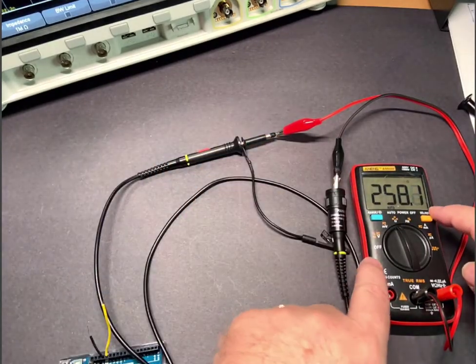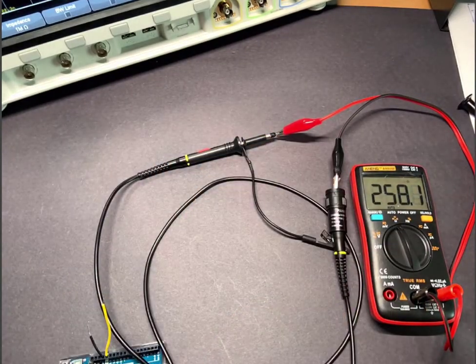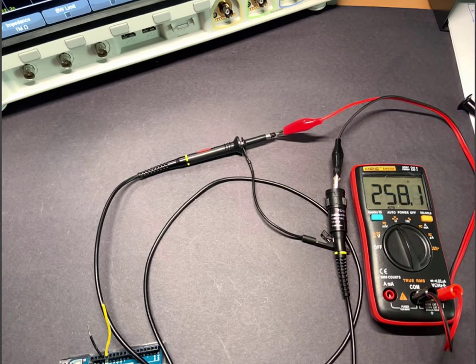And look at what that resistance is, 260 ohms. That is the series resistance of this cable. If you do this measurement with another coax cable, you will find a measurement on the order of 1 ohm or less. This is extra high resistance, and it's there in order to damp out any of the transmission line reflections in the cable.